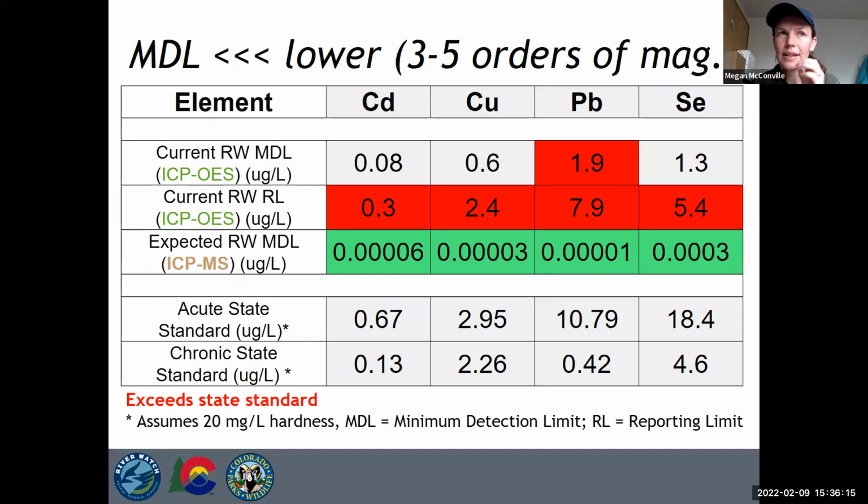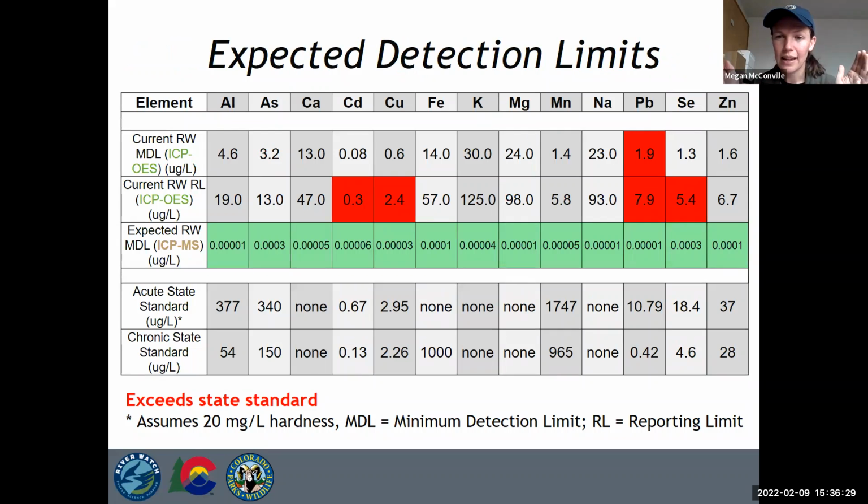Awesome. So there's a specific methodology that I follow that the health department and EPA have built and verified. Basically what I do is I take really small known concentrations of all 13 of our elements, and on successive days in the lab, so you get that fluctuation, it's a cold day, it's a warm day, how do we find consistency in what the instrument can do? And so I measure those routinely. I want 10 samples back to back to back to back of these really low concentrations.